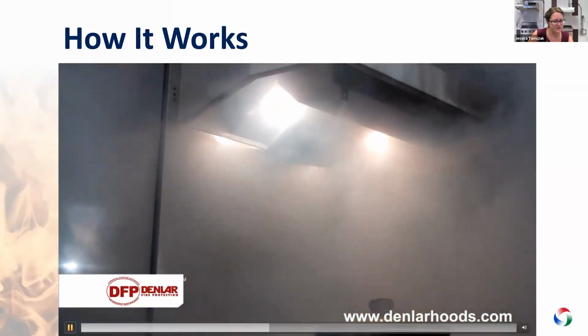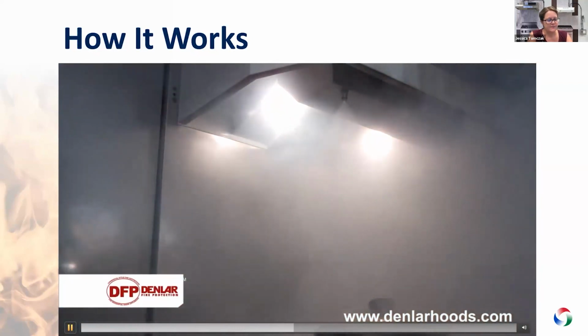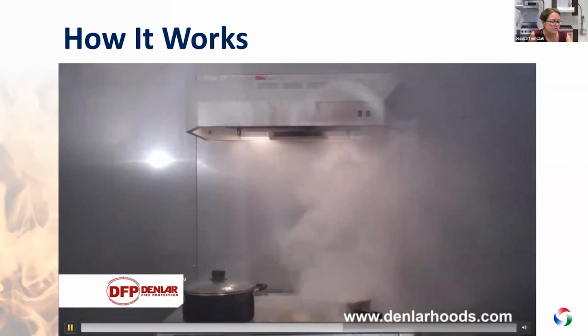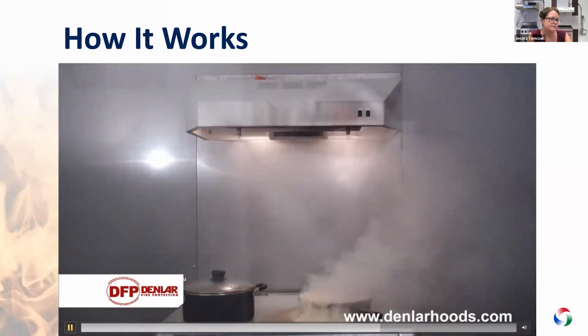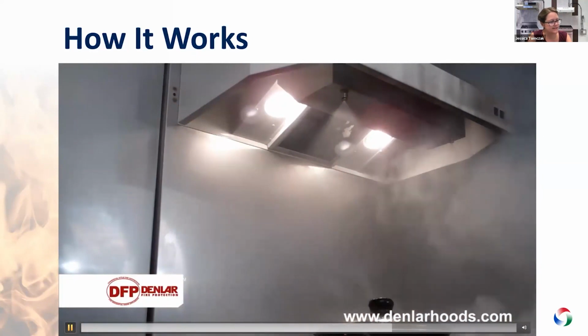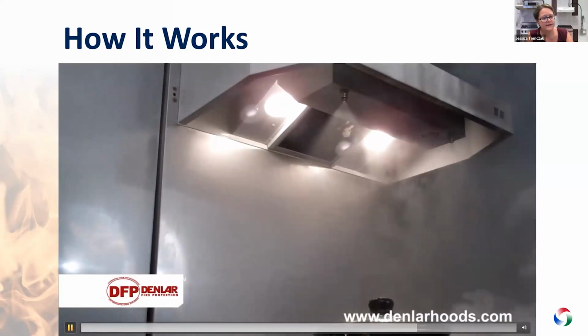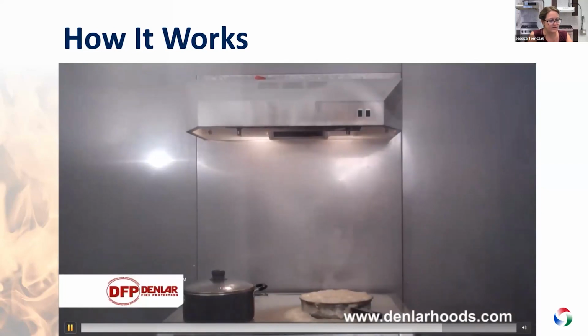When it pans out in a second, you're actually going to notice that there's this foam blanket on the stove covering the pan that was where the fire was. And this was a fire test from our facility, so this was just a pan of oil. But that foam blanket process is called saponification. What that does is prevent oxygen from getting onto that pan, so it prevents that fire from being able to ignite again. In addition to the suppression of the system, it also shut down the stove, and it's sounding an audible alarm, which there's no volume on this specific version, but normally if you were there, you would hear that. And it would also alert a fire alarm system if it was tied into one.